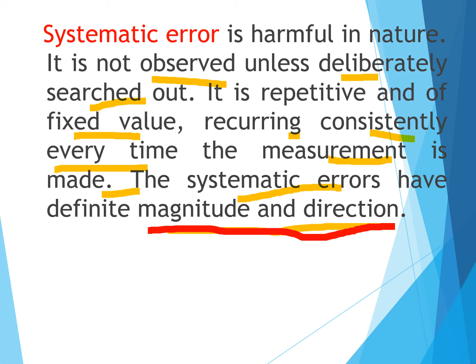The measuring instrument may go out of calibration with frequent use and also with subsequent aging. So due to age also, and due to subsequent use, the calibration may go out. Hence the measurement made with such an instrument will have an error which is called calibration error. Therefore an instrument should be periodically calibrated, to get rid of this calibration error.